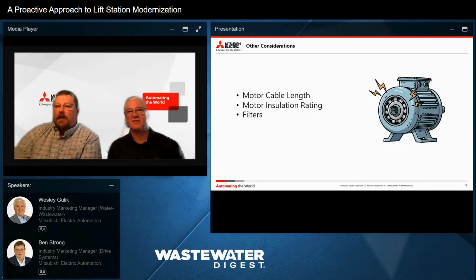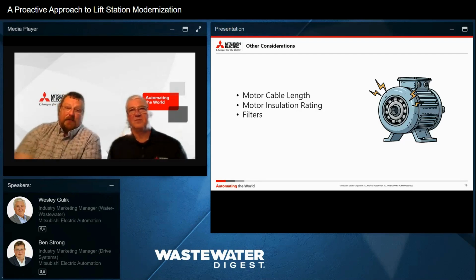to deal with the voltage spikes that can happen at the motor terminals. This really surprised me, but in water and wastewater, if you're retrofitting a lift station, you need to check the motor insulation rating on your pump motor, because there are still manufacturers out there that make motors that aren't rated for VFDs. If you're using a motor that's not rated for VFDs, you can actually get burn-through on the insulation in your windings, then you short your windings, and then the motor doesn't work anymore. So filters, motor cable lengths, and for some places, harmonic mitigation, depending on how big your lift station is. Those are all things we have to think about as we're modernizing our lift stations.